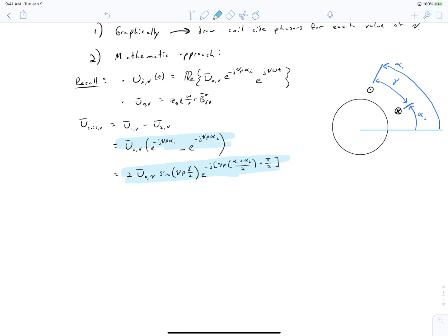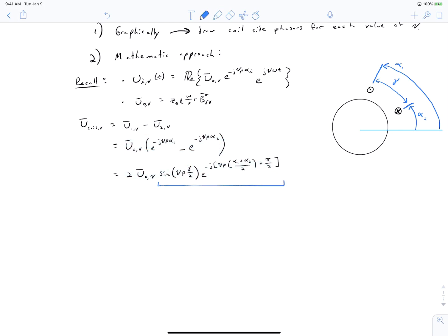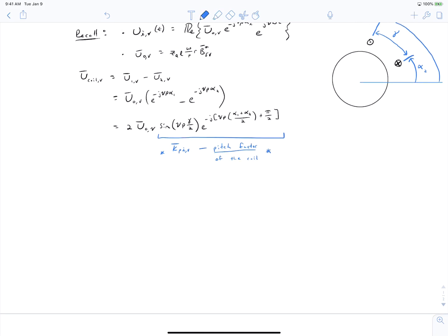It's easy to see how this is set up: when you have a coil at slot location alpha one or alpha two, you rotate the phasor by the negative of that angle. Doing the math, you convert this expression into a longer expression where one term is what we call the pitch factor of our winding. The pitch factor is called so because it directly relates to the pitch of the coil — how much space the coil spans, the value of gamma. If gamma equals zero, the coil has no pitch and links no flux. For a full pitch coil at the fundamental harmonic v equals 1, we define full pitch as gamma equals pi divided by p, which makes the sine term equal to one, giving a pitch factor magnitude of one.